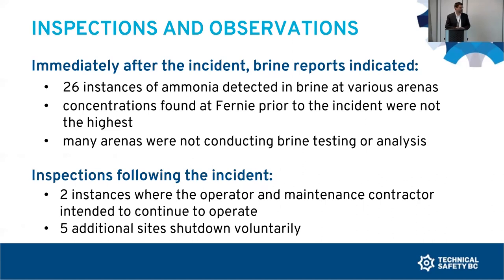We found, in obtaining evidence from brine analysis that looks for ammonia within the brine, 26 instances of arenas within the 3 years prior to Fernie actually containing ammonia within their brine system. So leaking chillers were occurring within industry. Many arenas were not conducting brine testing or analysis, so many people just were not aware that they may have had failures occurring within their systems until it showed up in a different way.